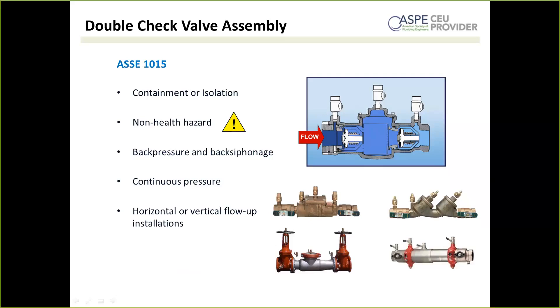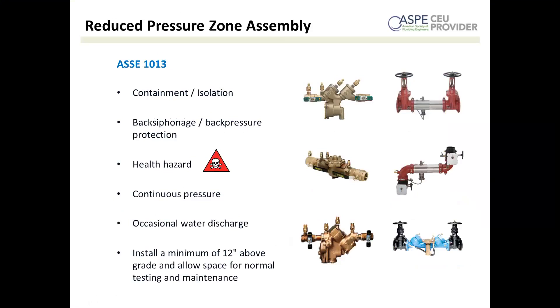For health hazard applications, we use a reduced pressure zone assembly. Other than an air gap, this affords the highest possible degree of protection. It's used for containment or isolation, handles back pressure and back siphonage, and is rated for health hazard applications as well as continuous pressure. The downside is that it will occasionally discharge water, and in a catastrophic event can discharge quite a bit — potentially causing flooding. It must also be installed a minimum of 12 inches above grade and typically cannot be installed vertically. It has test cocks and shutoffs like the double check — it's also an assembly.